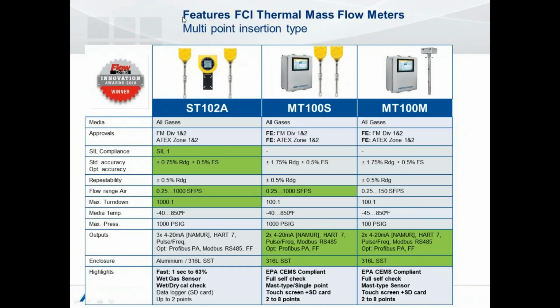Just like the other meters, we have a comparison sheet, things that set it apart. ST102A, part of that ST100 series family. Again, we've done some work. We have failure rate data to demonstrate compliance to IEC 61508. Quite a bit of difference in accuracy here, the 0.75% of reading. The MT100 is a 1.75% of reading device.